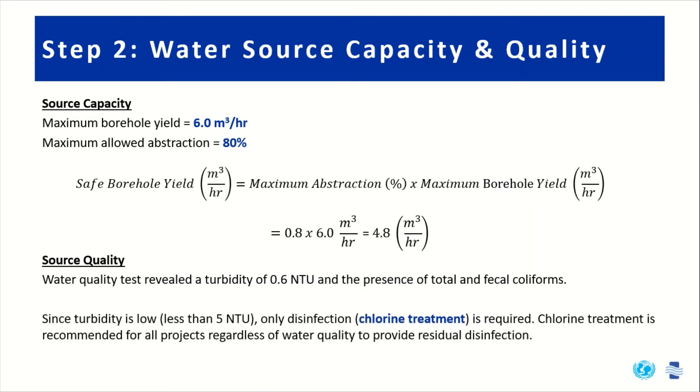We also conducted water quality tests, which revealed a turbidity of 0.6 NTU and the presence of total and fecal coliforms. Since the turbidity is low, less than 5 NTU, only disinfection, in this case chlorine treatment, is required.